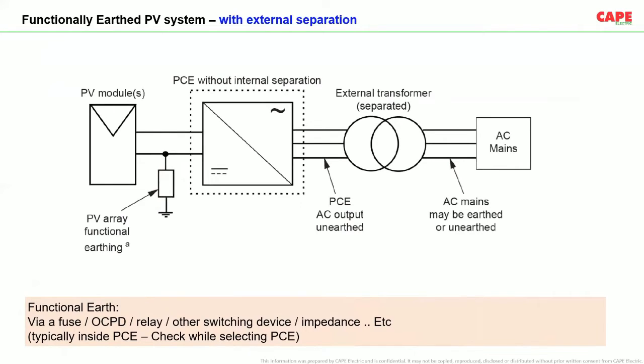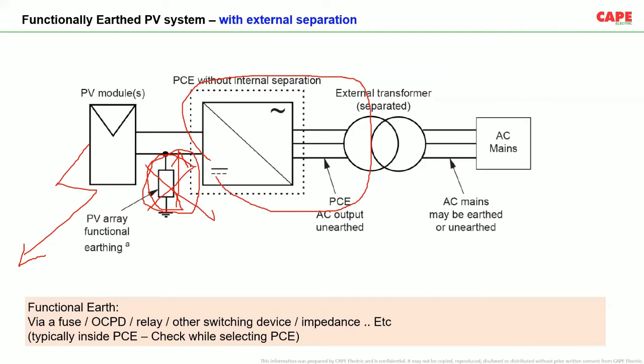Okay. Imagine in case of a fault here on the DC side, the fault current is returning back to the source through this functional earthing terminal. Let us say imagine there is a 1 amp fuse. So there is a functional earthing and there is a protective device in that particular circuit. Once the current is more than a certain limit, this device will disconnect the functional earthing. Number one, all of you, the user and the PCE and the electronics, know that the functional earthing has been disconnected because there is a fault somewhere in the DC side. Since the functional earthing is disconnected, there is no fault current flow. As a result, your system is still in.